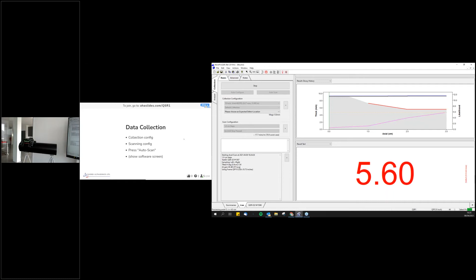The first one that the QSR1 has detected is an internal defect. So there is internal corrosion within this ex-service pipe. And there are also two further external defects on the bottom of the pipe that represent or simulate corrosion under pipe supports.